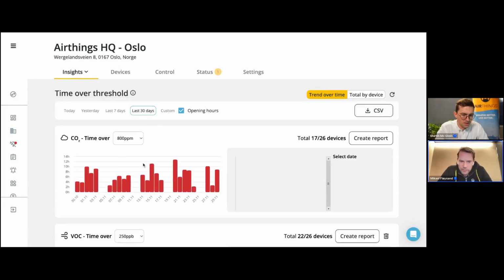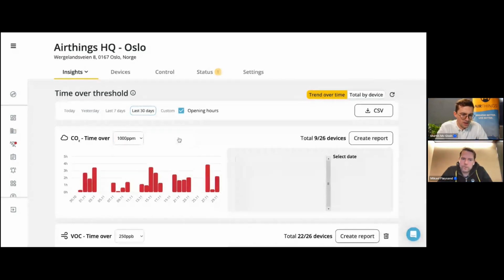So if you don't see anything above, say, 800, you could say 1,000 as well. It depends a bit on your... Maybe put it on 1,000, which I think is a more common threshold to work with than 800. So you see here, in this building, it's regularly slightly above. So no real over-ventilation here. But if this graph would show nothing, if there were never any measurements above 1,000 ppm, that would be a clear indication that you're over-ventilating.